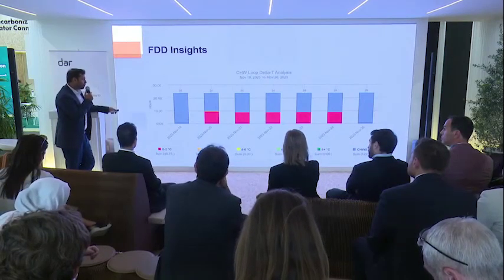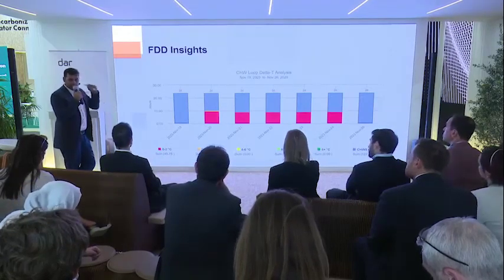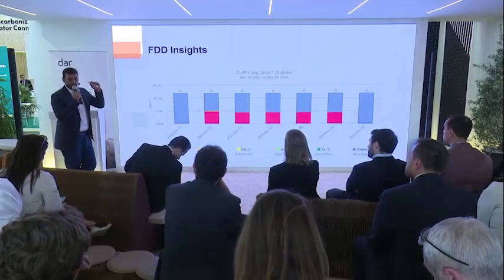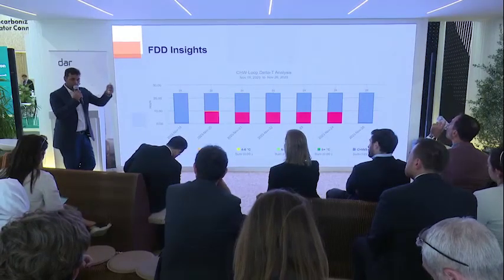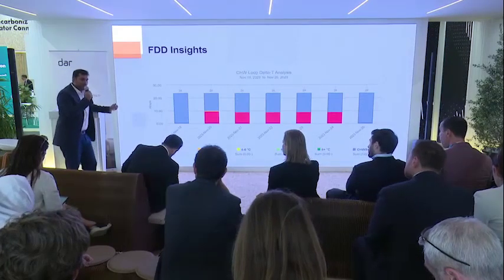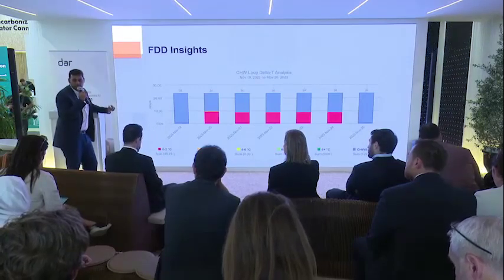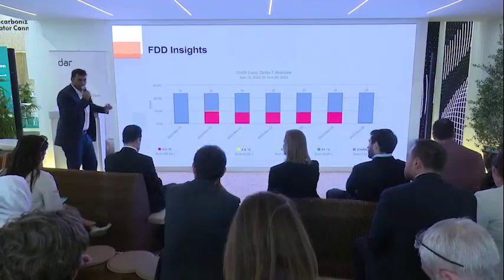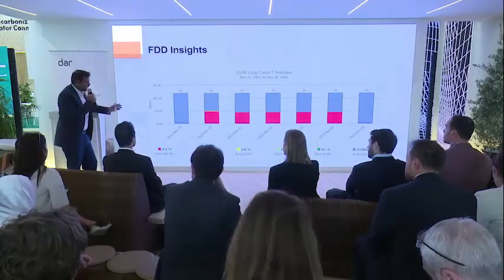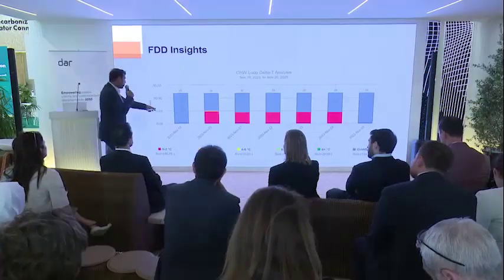So for those of you who are familiar with chillers or boilers, you know that these equipment have temperature, water or whatever other process variable you're tracking, temperature going out, temperature coming back in. If you have really low demand, then the temperature differential between the two loops will be very low, because you pumped water out at a particular temperature. There was no heat gain or heat loss, right? In this case, it did not give cooling anywhere else, and that's what we are tracking here.